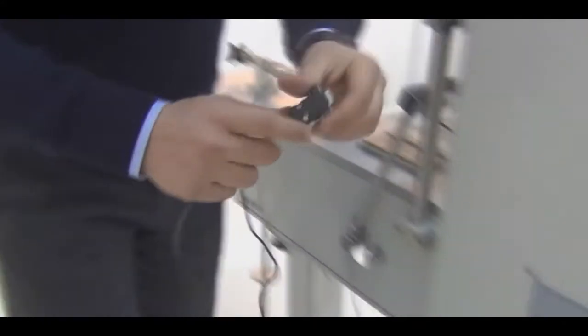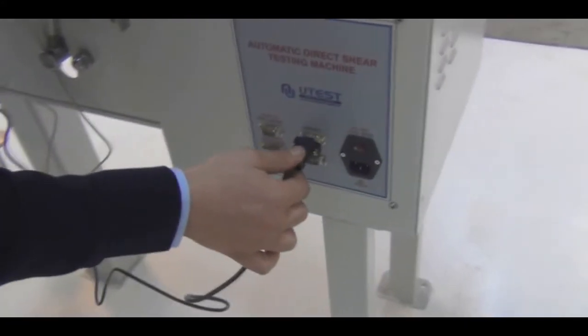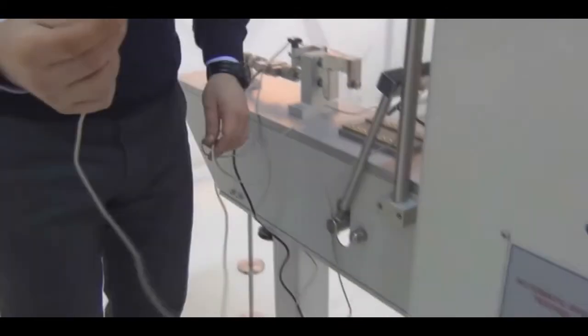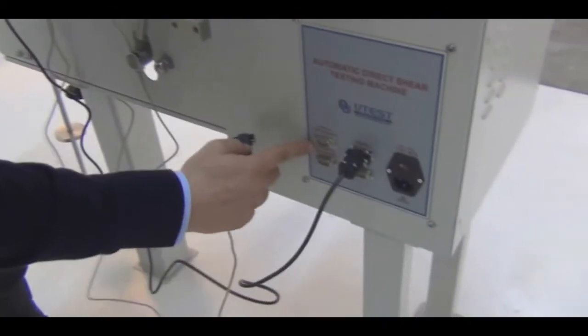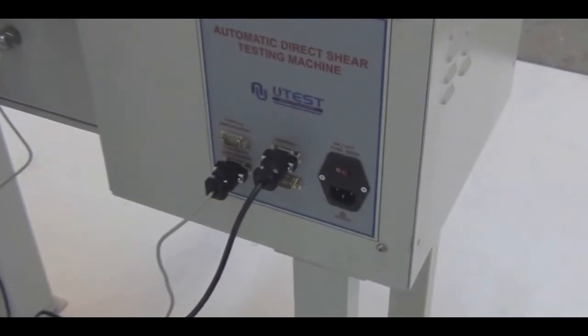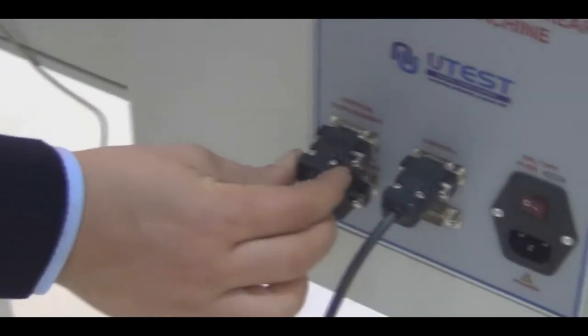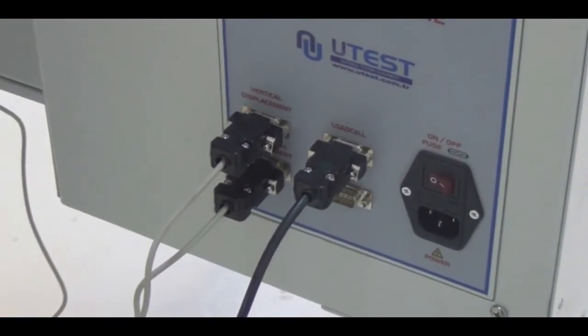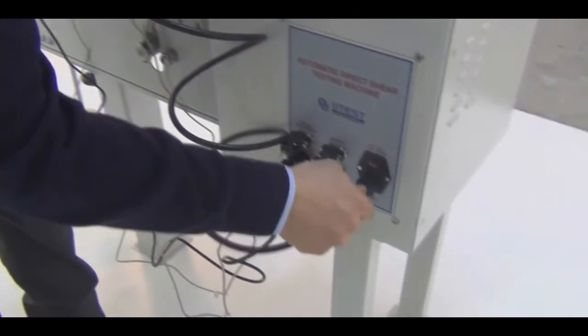Let's start inserting these into their places. For the load cell, it will be placed here. The second one is the horizontal displacement transducer, which will be placed into the horizontal displacement socket. The last one is the vertical displacement, which will be fixed here. We also have a power cable which is supplied with the machine.